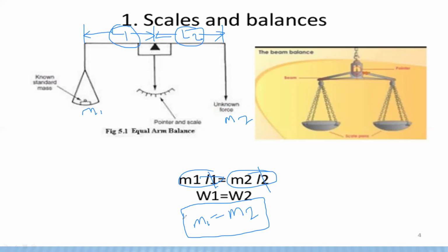Gravitational acceleration varies with geographical position. The variation is plus or minus 0.3% from the standard value at sea level. Hence, when using gravitational fields of different magnitudes, a slight correction can be observed. If the accuracy conditions demand it, the buoyant force due to immersion of the standard mass in air must be taken into account.